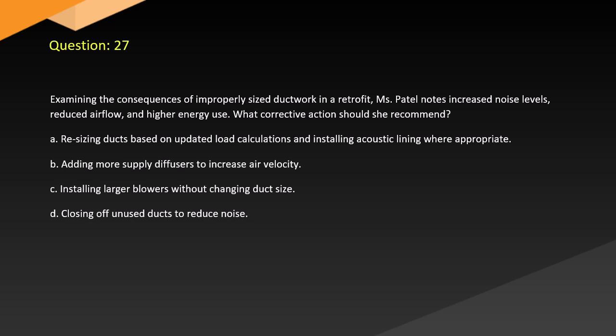Question 27. Examining the consequences of improperly sized ductwork in a retrofit, a technician notes increased noise levels, reduced airflow, and higher energy use. What corrective action should she recommend? A. Resizing ducts based on updated load calculations and installing acoustic lining where appropriate. B. Adding more supply diffusers to increase air velocity. C. Installing larger blowers without changing duct size. D. Closing off unused ducts to reduce noise.